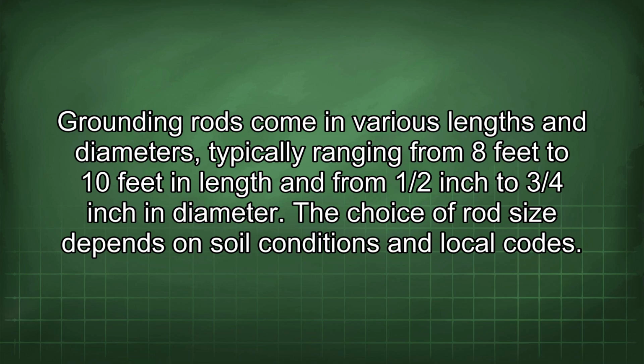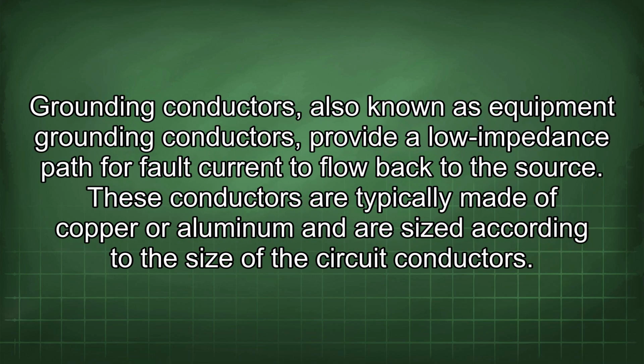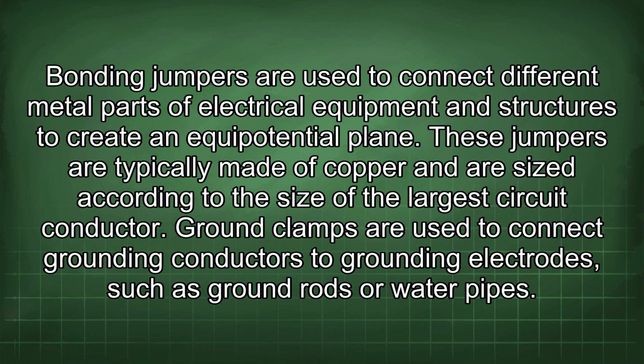Grounding rods come in various lengths and diameters, typically ranging from 8 feet to 10 feet in length and from 1/2 inch to 3/4 inch in diameter. The choice of rod size depends on soil conditions and local codes. Grounding conductors, also known as equipment grounding conductors, provide a low impedance path for fault current to flow back to the source. These conductors are typically made of copper or aluminum and are sized according to the size of the circuit conductors. Bonding jumpers are used to connect different metal parts of electrical equipment and structures to create an equipotential plane. These jumpers are typically made of copper and are sized according to the size of the largest circuit conductor.